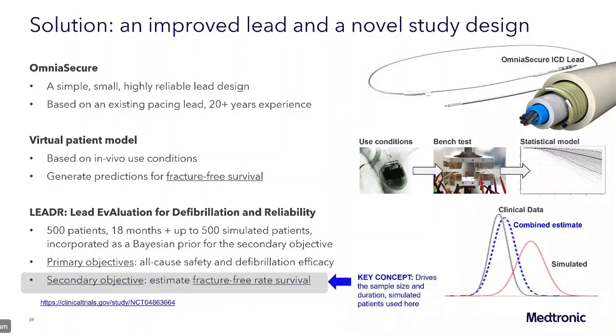Medtronic recently released a new ICD lead. The details aren't really important for this particular presentation, but the high-level attributes here are this was a lead that was designed to have extremely high reliability. It was based on an existing platform that already had a lot of data around it. So we weren't doing something entirely new, but rather we were able to look at what was done before and show that the adjustments that we were making were in the positive direction.